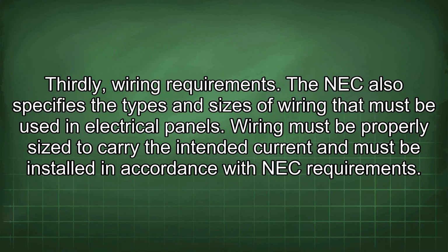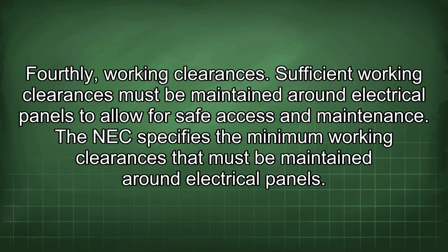Thirdly, wiring requirements. The NEC also specifies the types and sizes of wiring that must be used in electrical panels. Wiring must be properly sized to carry the intended current and must be installed in accordance with NEC requirements. Fourthly, working clearances. Sufficient working clearances must be maintained around electrical panels to allow for safe access and maintenance. The NEC specifies the minimum working clearances that must be maintained around electrical panels.